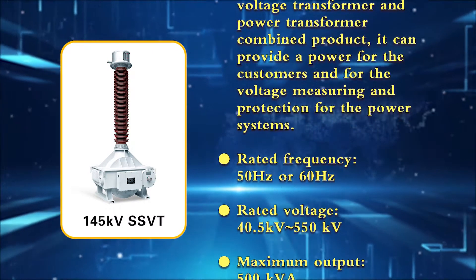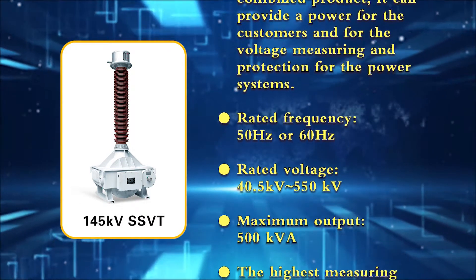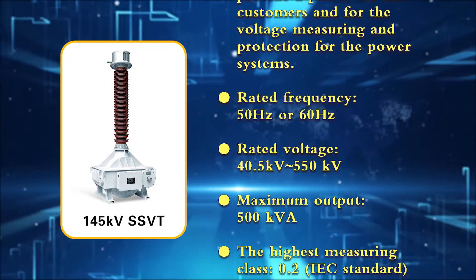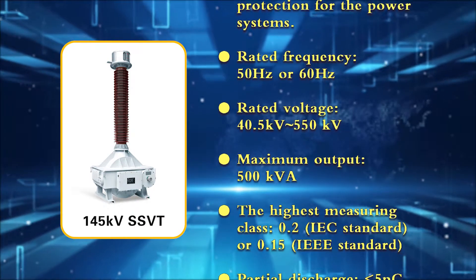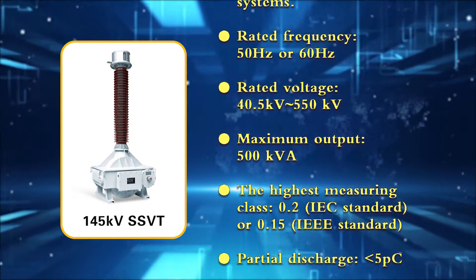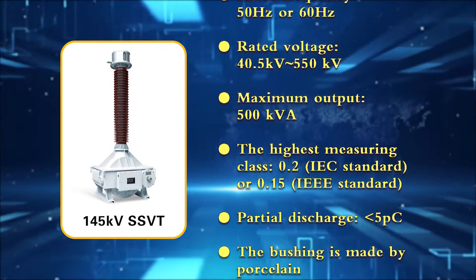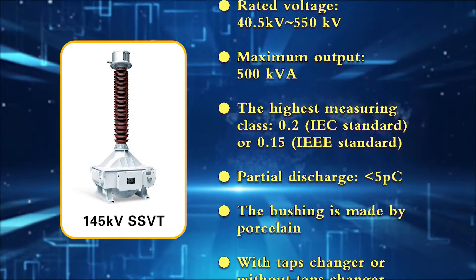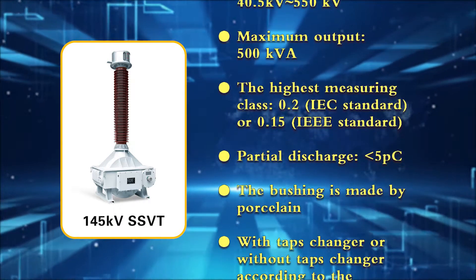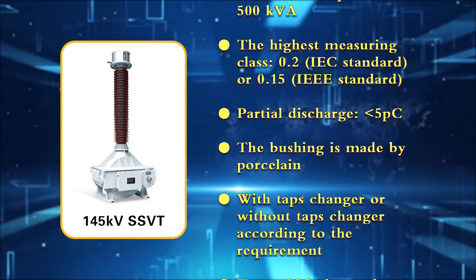Rated frequency: 50 Hz or 60 Hz. Rated voltage: 40.5 kV up to 550 kV. Maximum output: 500 kVA. Highest measuring class: 0.2 per IEC standard, or 0.15 per IEEE standard. Partial discharge: less than 5 pC.